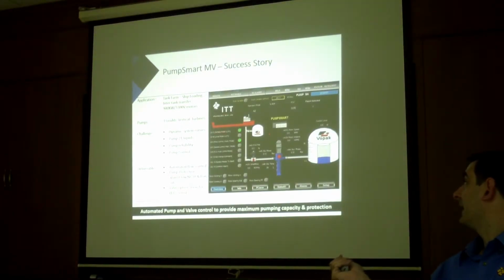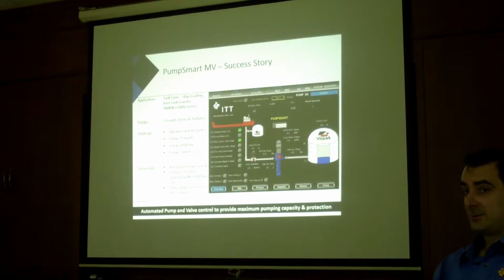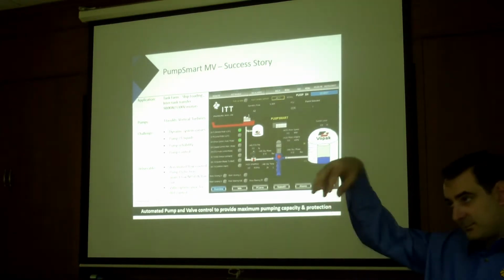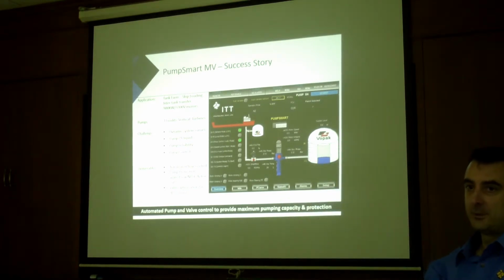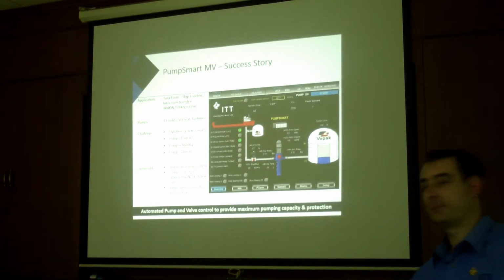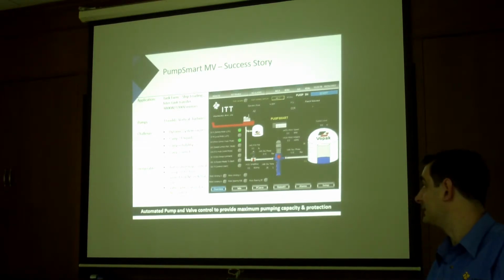This is Vopak in Singapore. They had 900 kilowatt motors, three pumps. This was an upgrade of an existing terminal. They increased the size of the pipe and they wanted more flow because they want to fill the boats up faster. So they went from 1,500 meters cubed per hour to 2,500. They changed the pump. ITT was very helpful for them because we managed to keep the same footprint and the same pit for the vertical pump. Other brands wanted a deeper pit, which means they had to dig out the hole. We didn't need to do that.